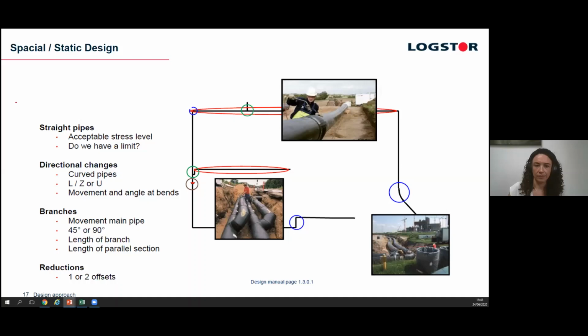So looking at the design, really, you've got your straight runs. What is the acceptable stress limit? Are you going to use a reduced one for a really increased service life? You might want to be going for 70 years or more. Or are you going to stick with standard codes?